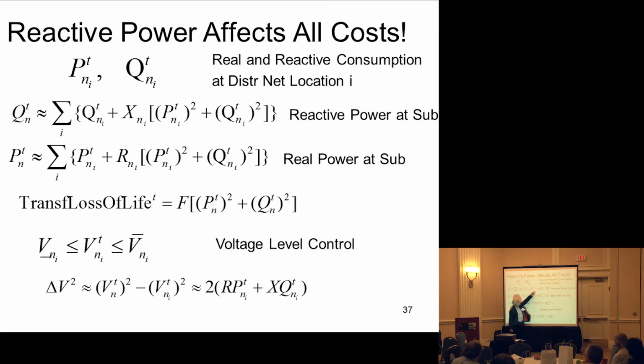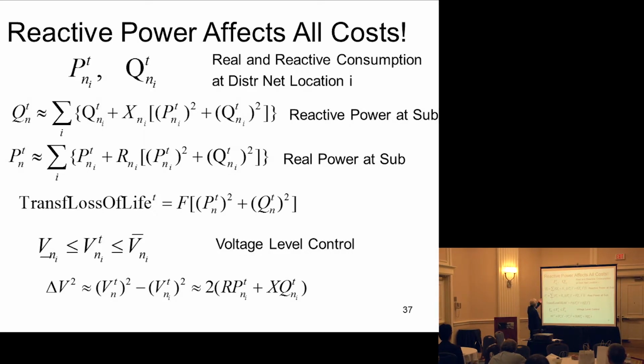And the reactive power lost is a function of real and reactive power. And it has a coefficient which is much higher than the coefficient that real power has. So this is why reactive power doesn't travel very far. Right? So ideally you would like to modulate this so that the losses are zero, and also so that you do not need to provide reactive power. So essentially, you have to produce a little bit more than the reactive power consumed, so as to cover the reactive power that will be consumed over the distribution lines.